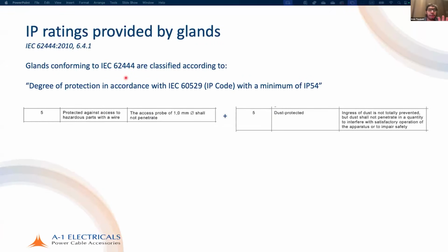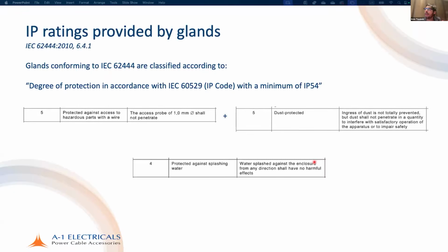So if you select a gland according to IEC 62444, it has to meet this requirement as per its product standard. Now, IP54: the first digit is 5, the second digit is 4. Protection against splashing water. Any water splashed against the enclosure from any direction shall have no harmful effects. Again, remember the third letter is optional, so there is no third letter, it's just IP54.